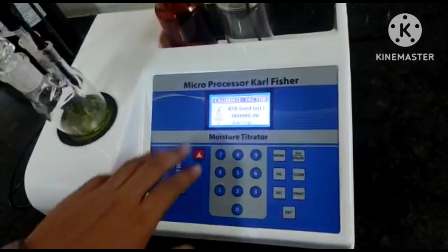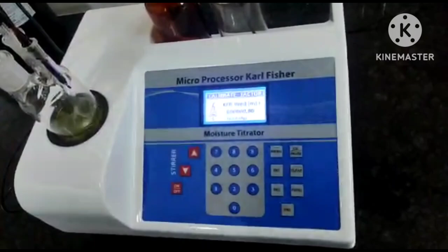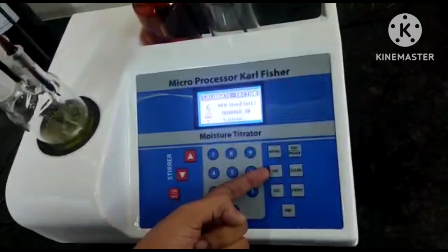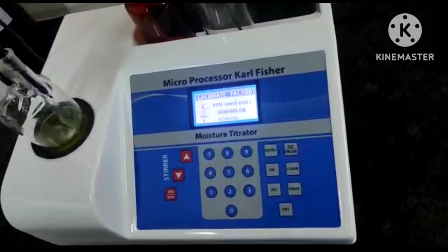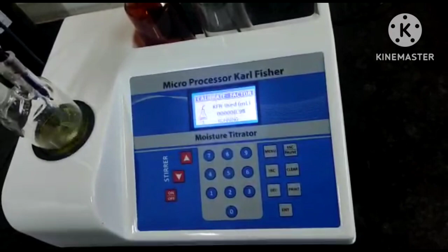A waiting signal is coming, so you have to wait. This first option means you are doing this calibration for the first time. If you want to repeat it 2 or 3 times, then after the first reading you have to press the increase button, and then you can repeat another distilled water calibration for taking the average value, the RSD value. So this is the first time, so we have to wait to get the neutralizing point, and then we will start with the next one.